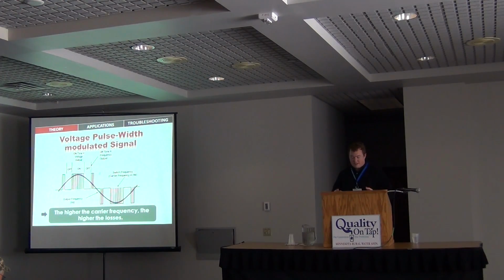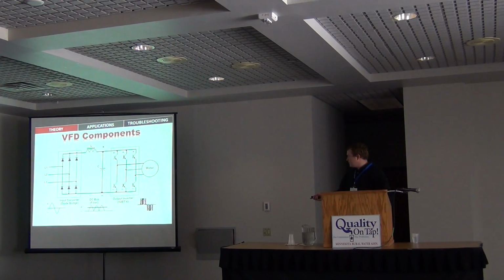And then the off time is actually the supplied frequency from the drive. So by adjusting that off time of these pulses, we can change the speed of the VFD, and this is all done internally in the drive with what it's created to do. But it's kind of interesting. And then these little fast switches you see are all these IGBTs, which are insulated gate bipolar transistors. Doesn't matter, but they switch really fast.